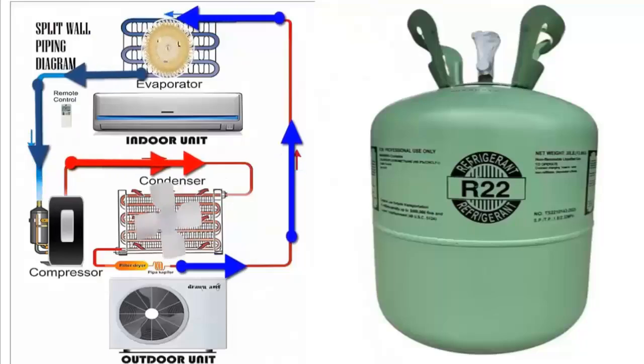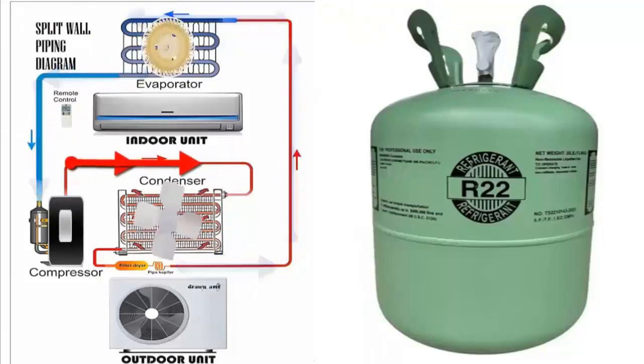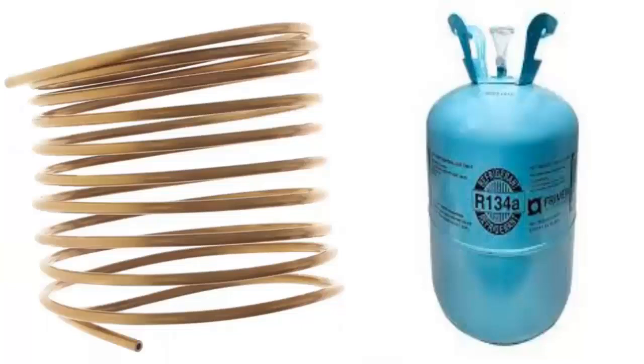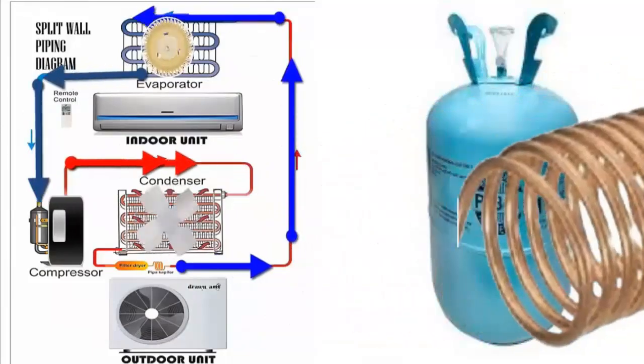3. Under normal conditions, with the same cooling capacity, the capillary tube with R134a should have a larger internal diameter or a shorter length compared to the R22 capillary tube. However, since the cooling capacity of the equipment will be lower, the original R22 capillary tube can be tested and adjusted if necessary to achieve the appropriate working temperatures with R134a.